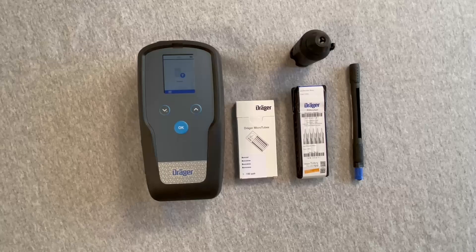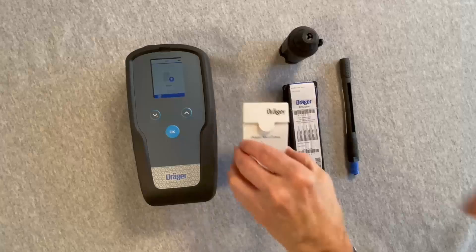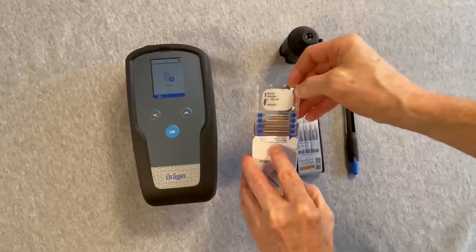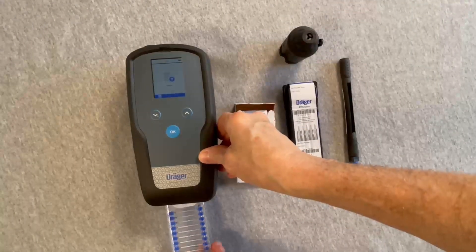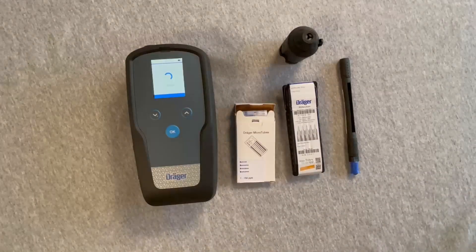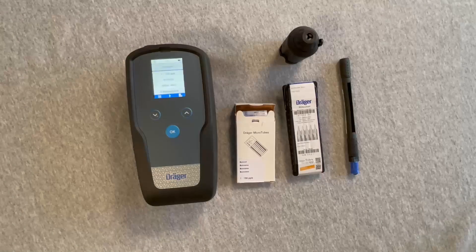The booster tube is connected to the X-am 7000 using the pre-tube holder assembly just before taking a measurement. Insert the microtube into the device. The display will show the specific microtube — in this case, the low-range PPB benzene microtube.